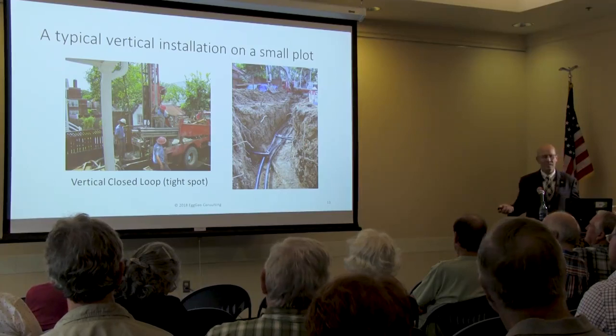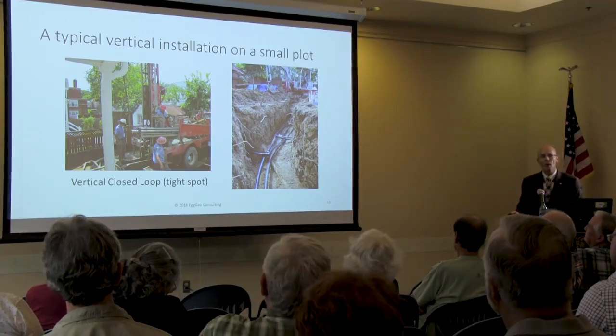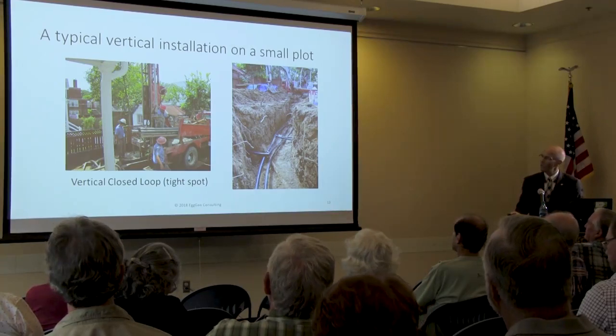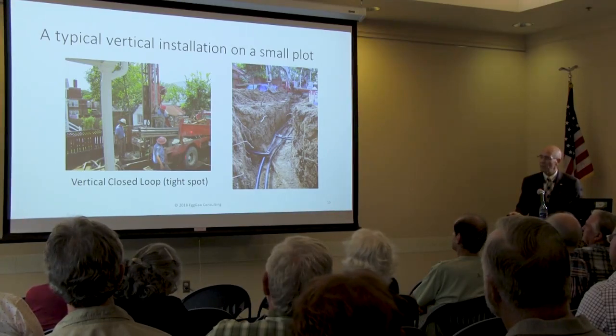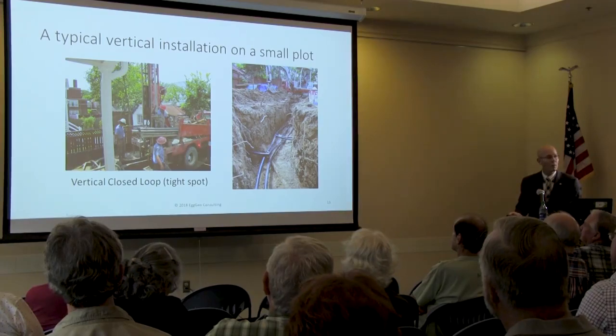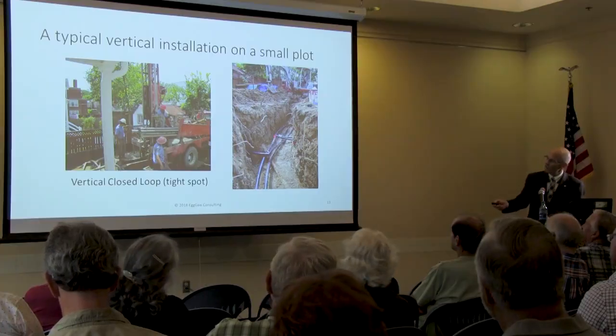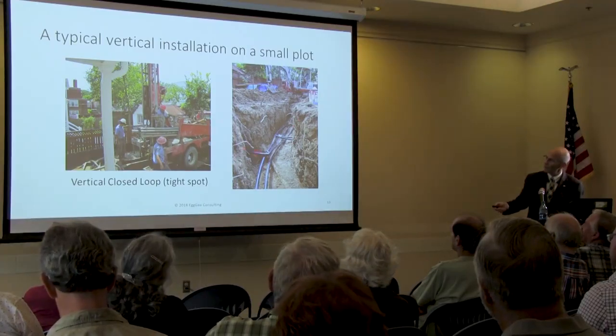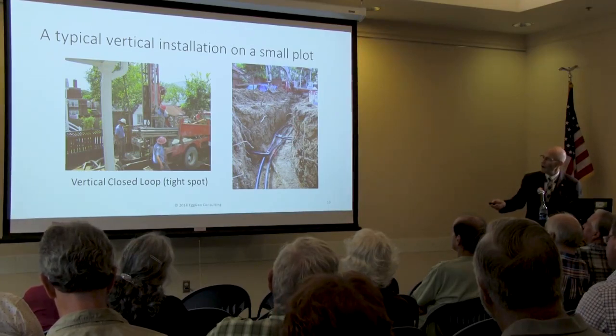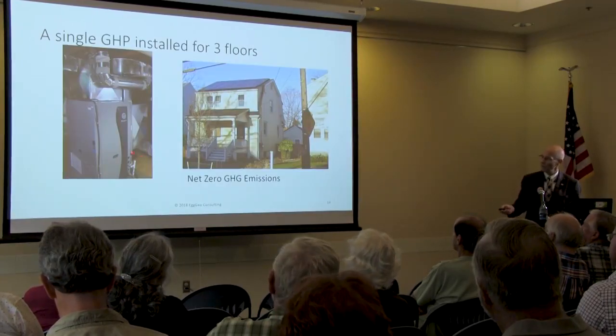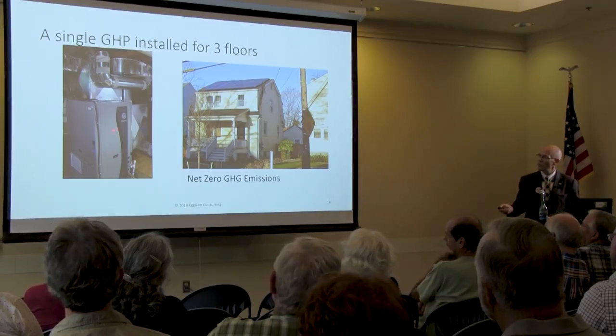Okay, so this is a typical vertical installation. Probably most of us have seen a geothermal drill rig, and this is typically what they look like. It looks like a water well drill rig. When we're doing a vertical system, they're called boreholes. They're not wells, they're boreholes, because into the borehole, and you'll see a picture of this a little bit later on, there is a pair of pipes that are closed loop. Then the pipes, and you can see pairs of pipes coming out through this header trench, going different ways, are all tied in and brought back into a building where they go to a geothermal heat pump.